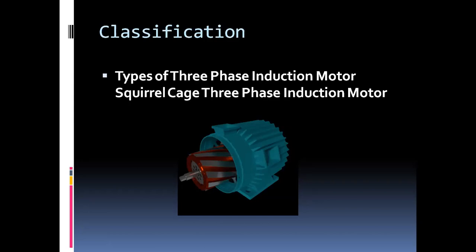Almost 90% of induction motors are squirrel cage type, because this type of rotor has the simplest and most rugged construction imaginable and is also indestructible. The rotor carries rotor conductors, which should be clearly noted are not wires, but heavy bars of copper, aluminum, or alloys.